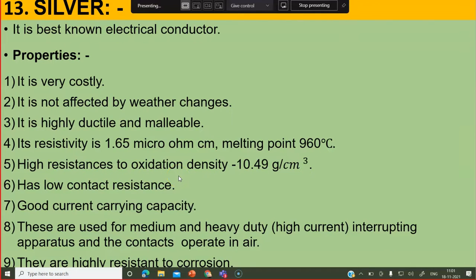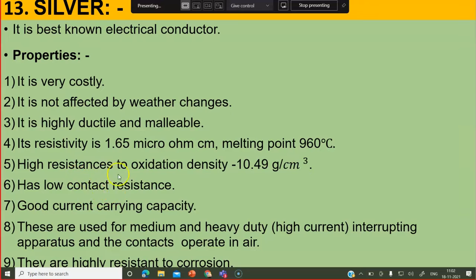Why is silver preferred over other materials? Because of its resistance to oxidation. Density is moderate. It has low contact resistance, which is also a very important property. For contacts, silver layers are used. Whatever material you are using, you can just coat it with silver, and your contact resistance will be very less and oxidation resistance will be very high.